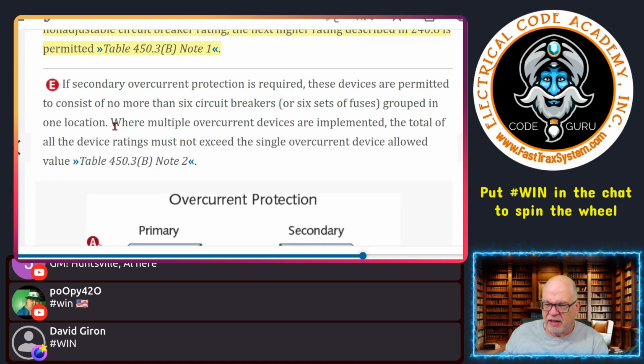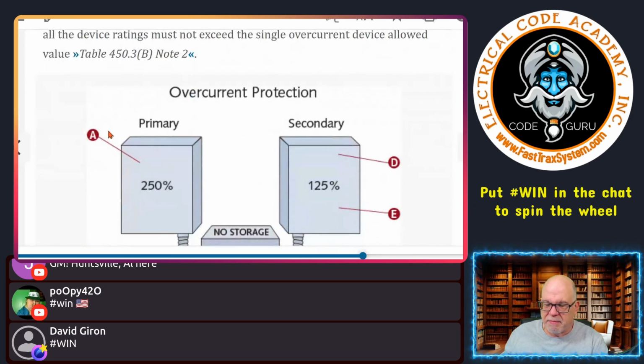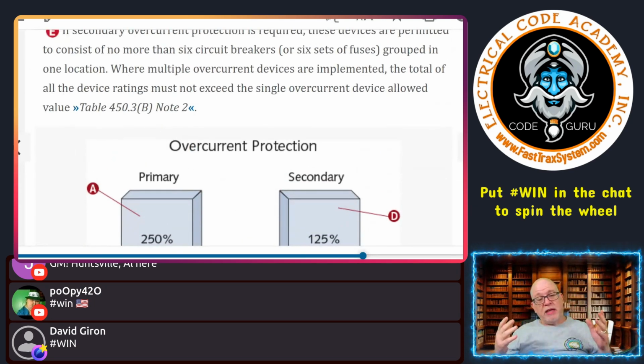Grouped in one location. Now, it says where multiple overcurrent devices are implemented, the total of all the device ratings must not exceed the single overcurrent device allowed value. So what that means at the end of the day is if you're doing a load calculation, let's say this is a 200 amp panel, then I can't have individual breakers, if I have up to 6 of them, exceed what would be the requirement if it was a single overcurrent protective device. Yes, I can have the multiples in there, but it's not like you can go crazy. It still cannot exceed the value. Where is that? Now let's go over and look at the code. Where does that say that?